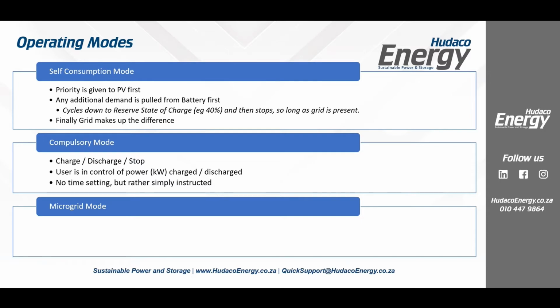You are in charge of not only the operation, the charge, discharge, or stop, but also the amount of kilowatts being charged or discharged at that time. So maybe you want to drain your batteries for some reason, or charge your batteries manually. You can say, I want to charge my batteries, but I only want to charge at 3 kilowatts. Maybe you're on a time of use tariff, or on a peak demand charge. If you say, I don't want to exceed 3 kilowatts or 1 kilowatt or 4 kilowatts or 8 kilowatts, whatever it is, it will pull that power from wherever. Much like the forced charge mode, it will pull this power straight from the grid and bring it in.